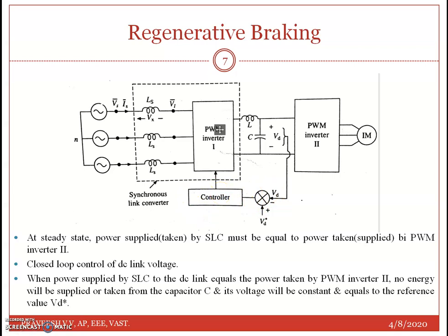Now assume the load on the induction motor is increased. The power taken by PWM inverter 2 from the DC link will be higher than the power supplied by SLC, so the capacitor voltage Vd will fall below reference value Vd*. The closed loop voltage control will increase the value of IS. The increase in IS restores power to the DC link and brings the DC link voltage back to the reference value. Since the SLC works as a boost converter, the closed loop control of DC link voltage provides drive ride-through capability against voltage sag or under-voltage.